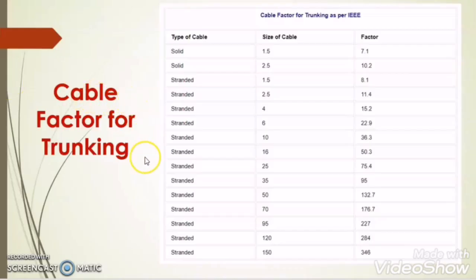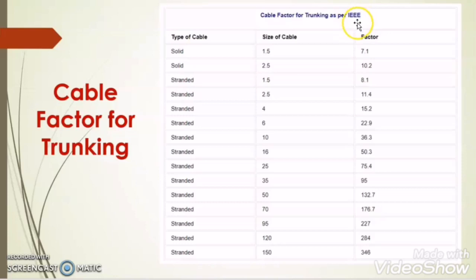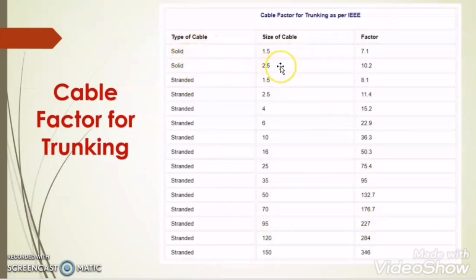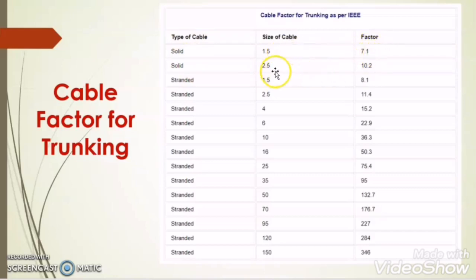The cable factor for trunking as per IEEE standard — from this standard, there is a factor mentioned for different sizes of single core wires. For solid 1.5mm, the factor is 7.1, and for 2.5mm, the factor is 10.2.